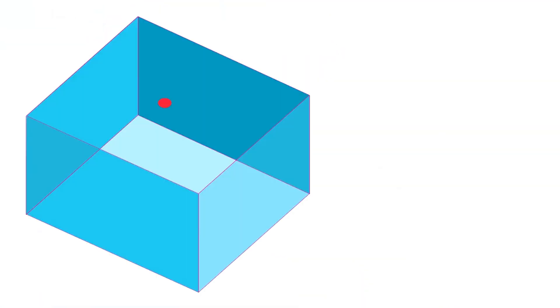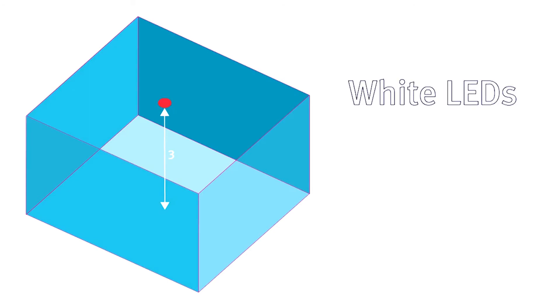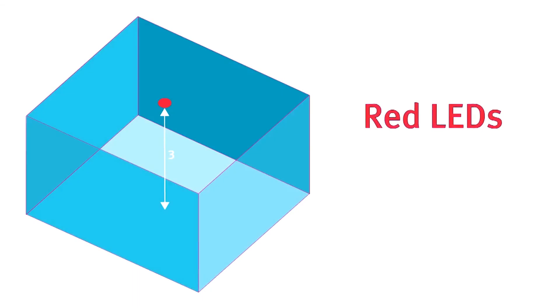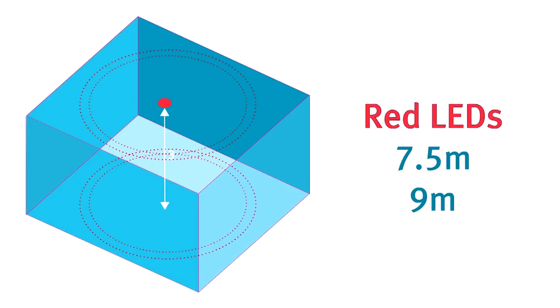Both devices have the capability of variable coverage volumes, and this helps simplify the range. For the ceiling beacons, these volume coverages are all based on a maximum ceiling height of 3 metres. So subject to control panel compatibility, you can set the coverage of a white LED beacon to 5, 7.5 or 10 metres diameter. For red LED beacons, this coverage could be set to 7.5 or 9 metres diameter.